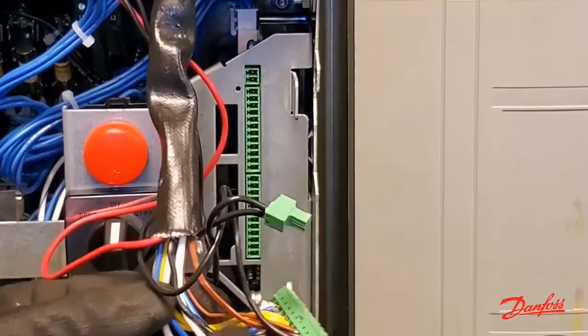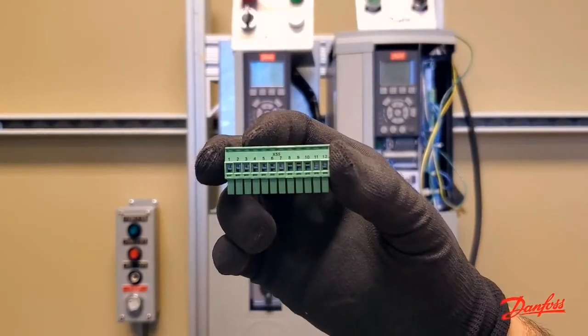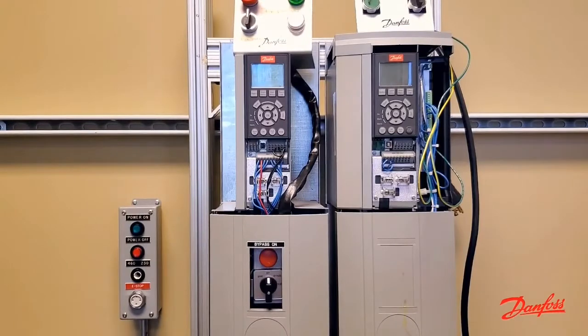These require just a standard set of dry contacts, and if they're found empty and or without any jumpers in them, that's probably the reason why the system won't run.